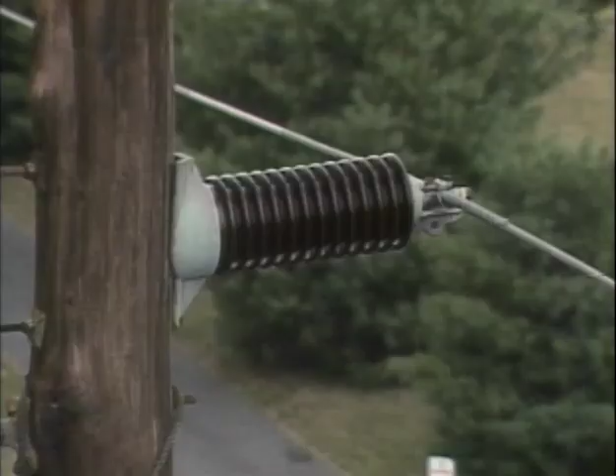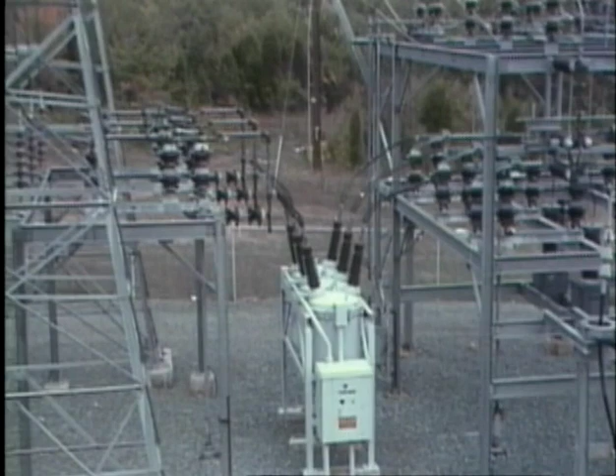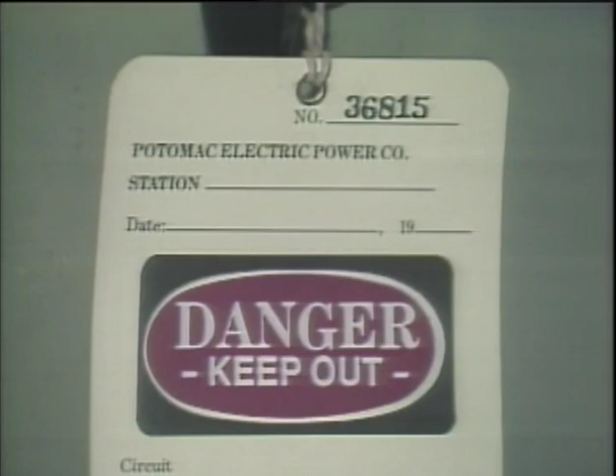In this situation, a 69 kV circuit must be de-energized so that the insulators can be replaced on several poles. The dispatcher coordinates the switching and tagging for this job. To de-energize the circuit, he operates a control switch that in turn operates the appropriate circuit breaker. This opens the circuit. Then he tags out the breaker. To isolate the circuit, a disconnect switch is opened, and it's tagged out. Once the circuit is opened, isolated, and tagged out, the dispatcher is notified so he can report the status of the circuit to the field crew.